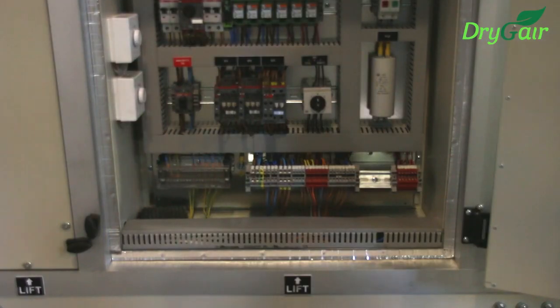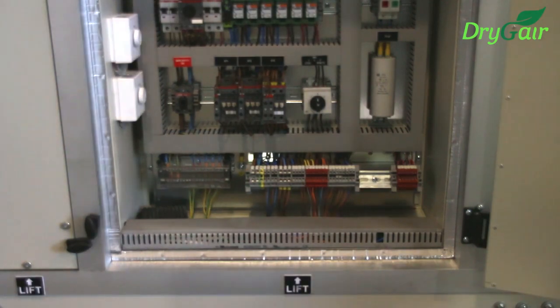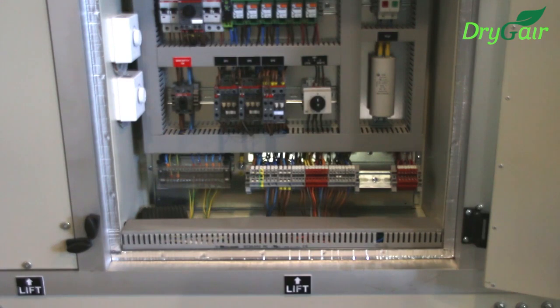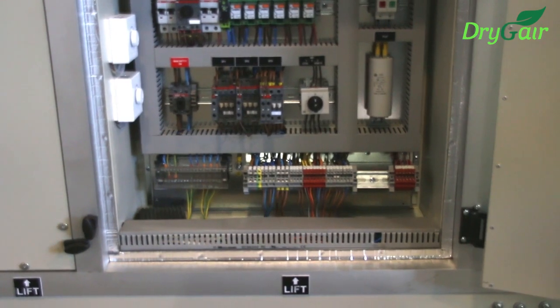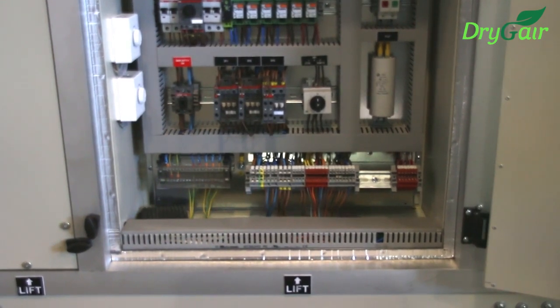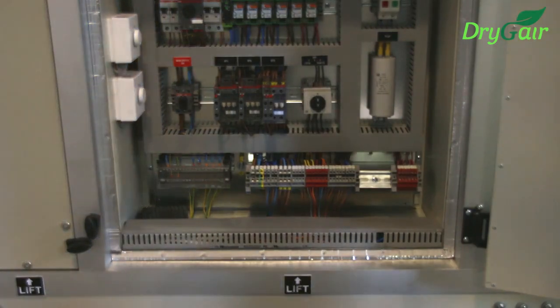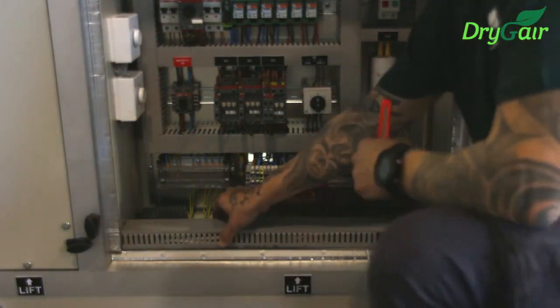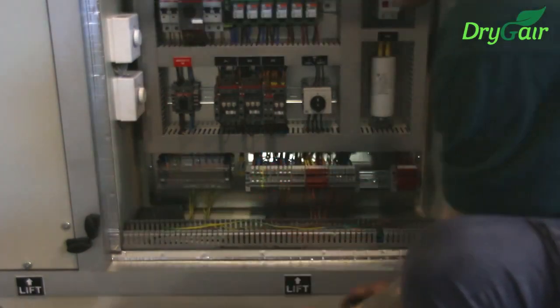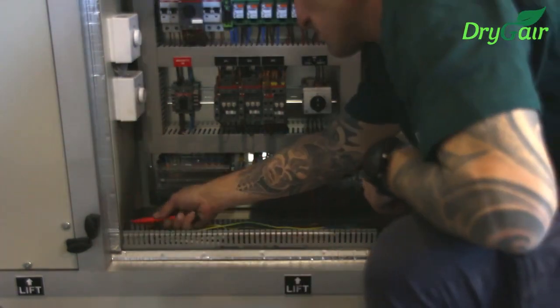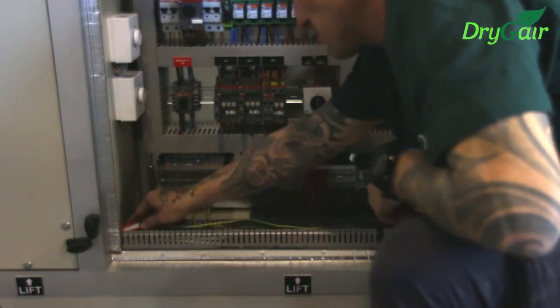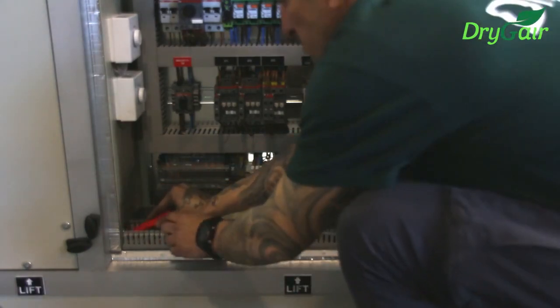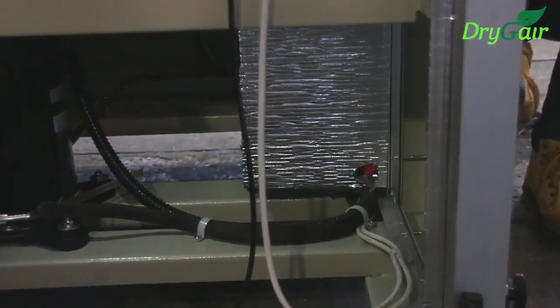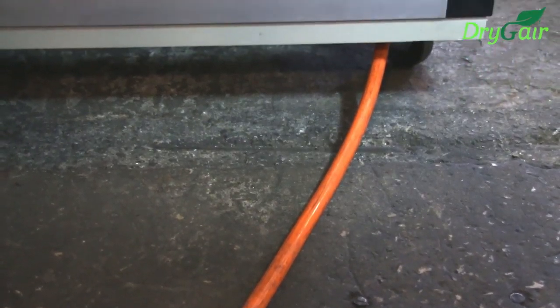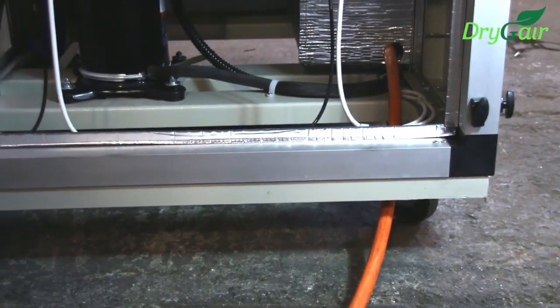Before hooking up the unit to the main power supply, verify that the external circuit breaker is turned off. Connect the main cable to the prepared external circuit breaker. Down at the bottom, you will identify a covered compartment containing the electric wires. Remove this cover. Use a retractable utility knife to cut a small hole in the silver insulation layer on the left side of the compartment. Feed the power cable through this hole and into the electric compartment.